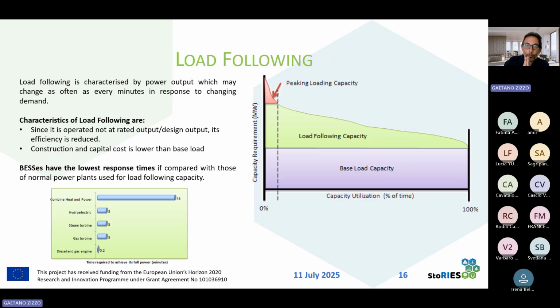Another service is load following. If we study the daily load profile, we see that we need a base load capacity, a load following capacity, and a peaking load capacity. So we need power plants able to produce an almost constant power during the whole day. We need power plants that are able to modify their production very quickly, in a few minutes, for following the load. And then we need power plants that are used only for providing power in extreme situations, for compensating peaks of load.